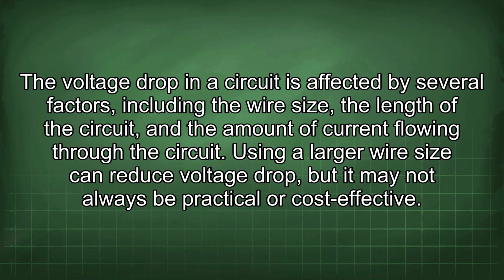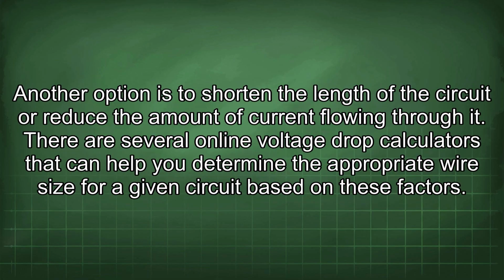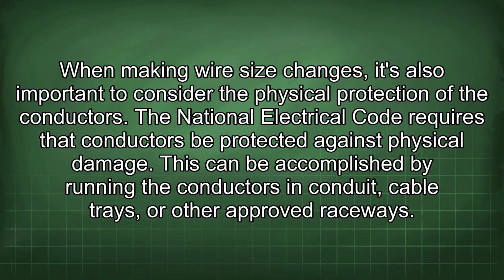Using a larger wire size can reduce voltage drop, but it may not always be practical or cost-effective. Another option is to shorten the length of the circuit or reduce the amount of current flowing through it. There are several online voltage drop calculators that can help you determine the appropriate wire size for a given circuit based on these factors. When making wire size changes, it's also important to consider the physical protection of the conductors.